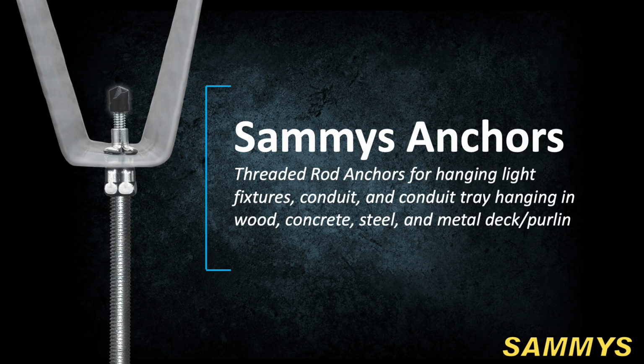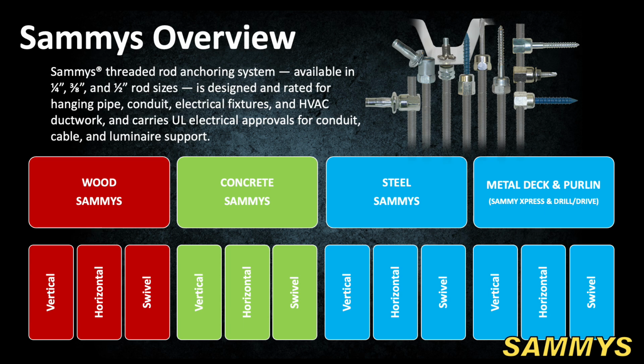designed for that material. Sammys threaded rod anchors come in 1/4 inch, 3/8 inch, and 1/2 inch rod sizes and are engineered for overhead and side mount applications. They're designed and rated for hanging pipe, conduit, lighting, bus duct, cable tray, and junction boxes. Sammys carries UL electrical approvals for conduit, cable, and luminaire support, so you're not just using a generic hanger, you're using a system that's been tested for the types of loads and applications you actually see in the field.